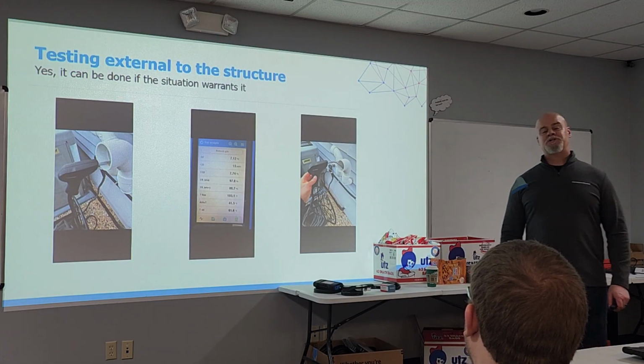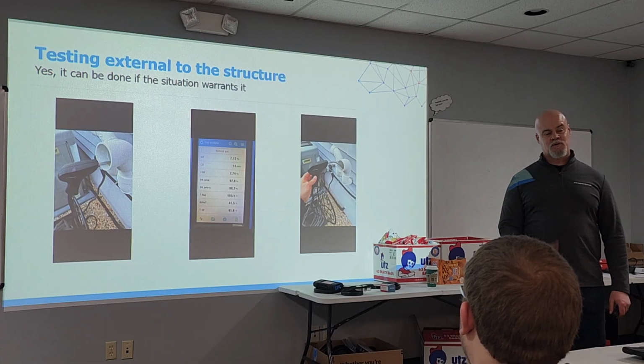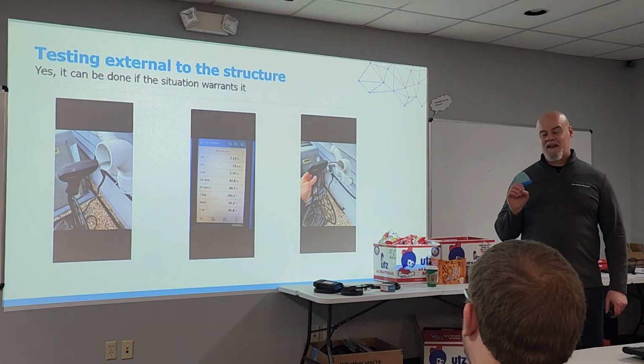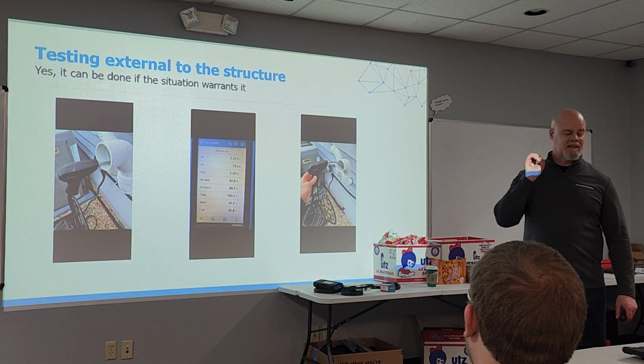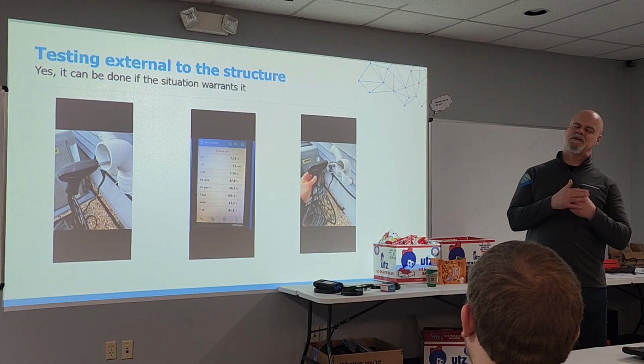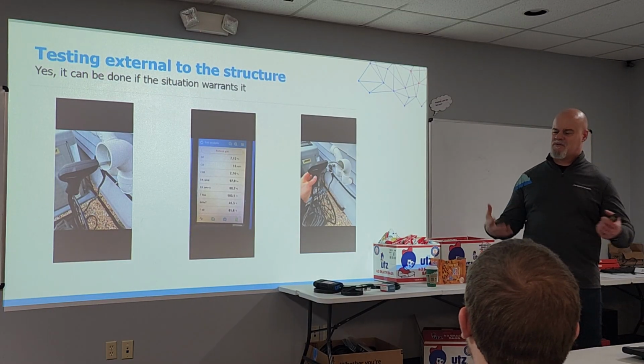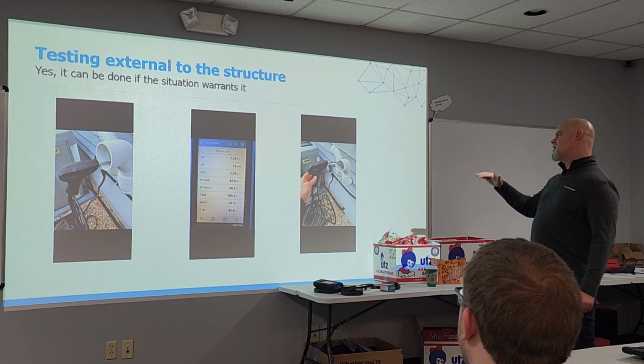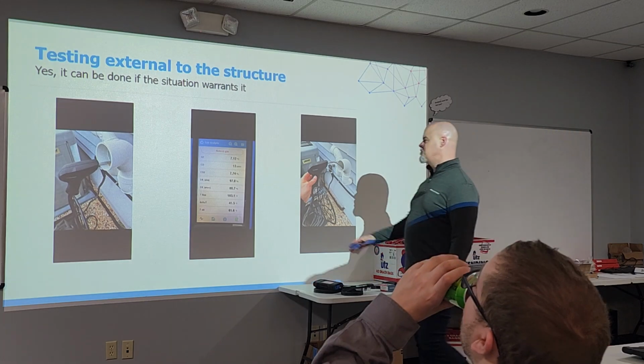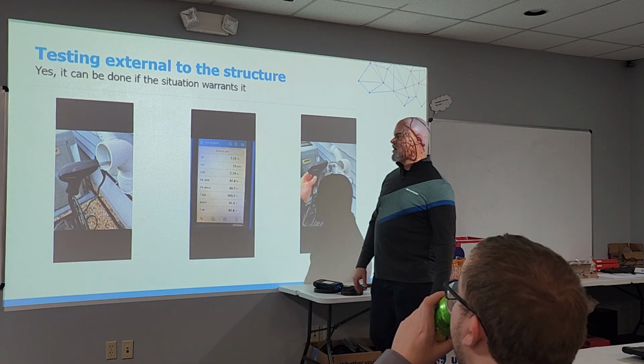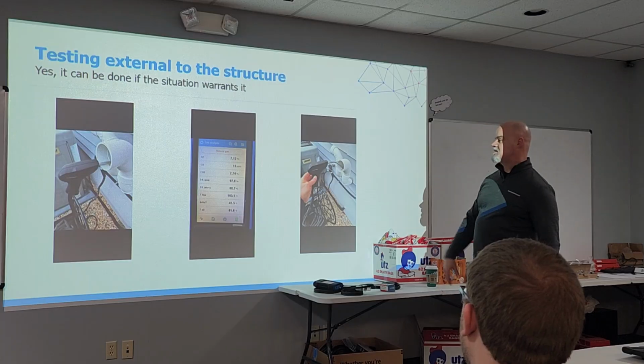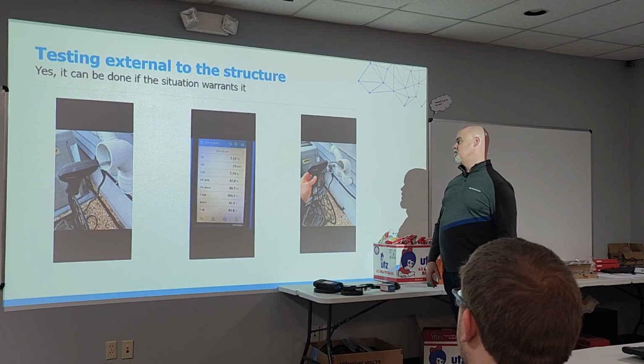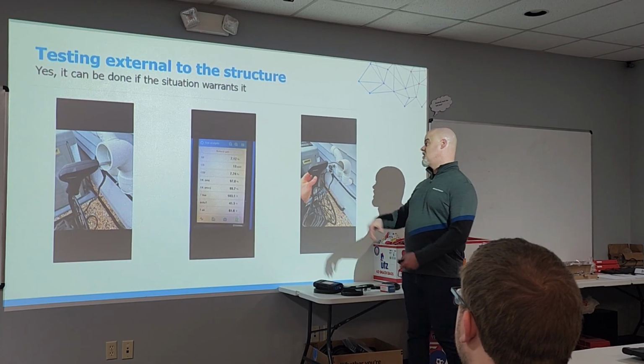Now, I much prefer you testing inside all day and twice on Sunday, but if you have an application that doesn't allow you to do it, whether it's too tight and you don't want to put your fluid in, or you just feel uncomfortable, and you have access to the outside, you can test from there. You just have to get your probe far enough into the exhaust to be able to test. This is my residence, and as you can see, shoemakers' kids go without shoes, but that's a nice 18 SEER Lux air condenser right there.